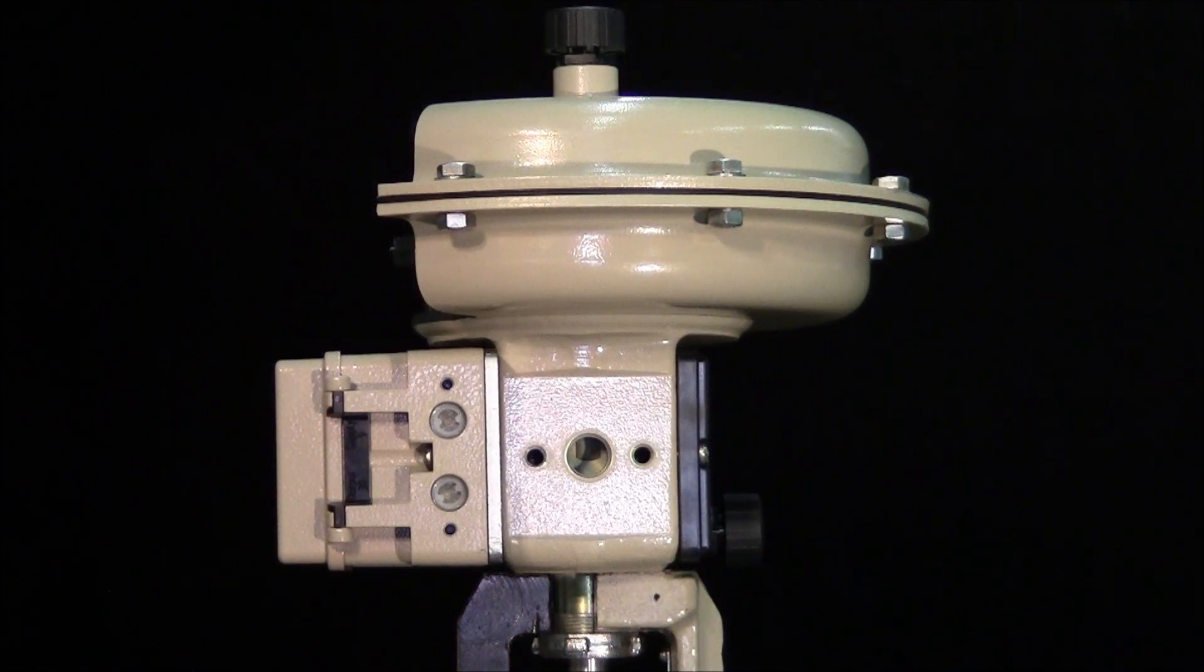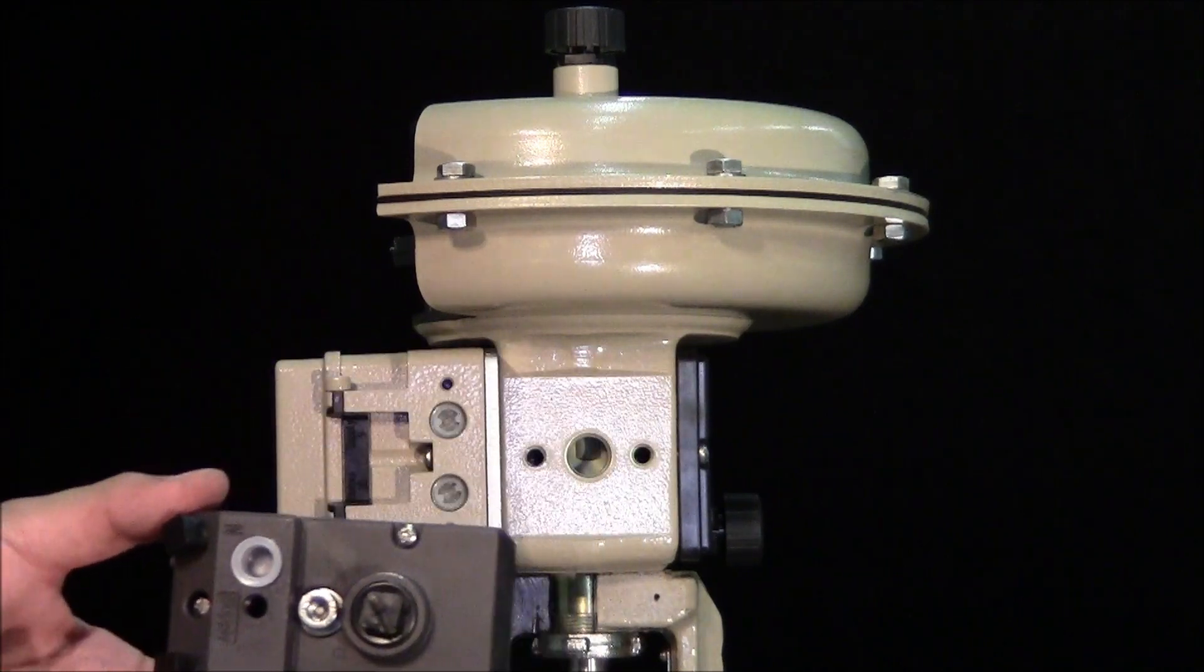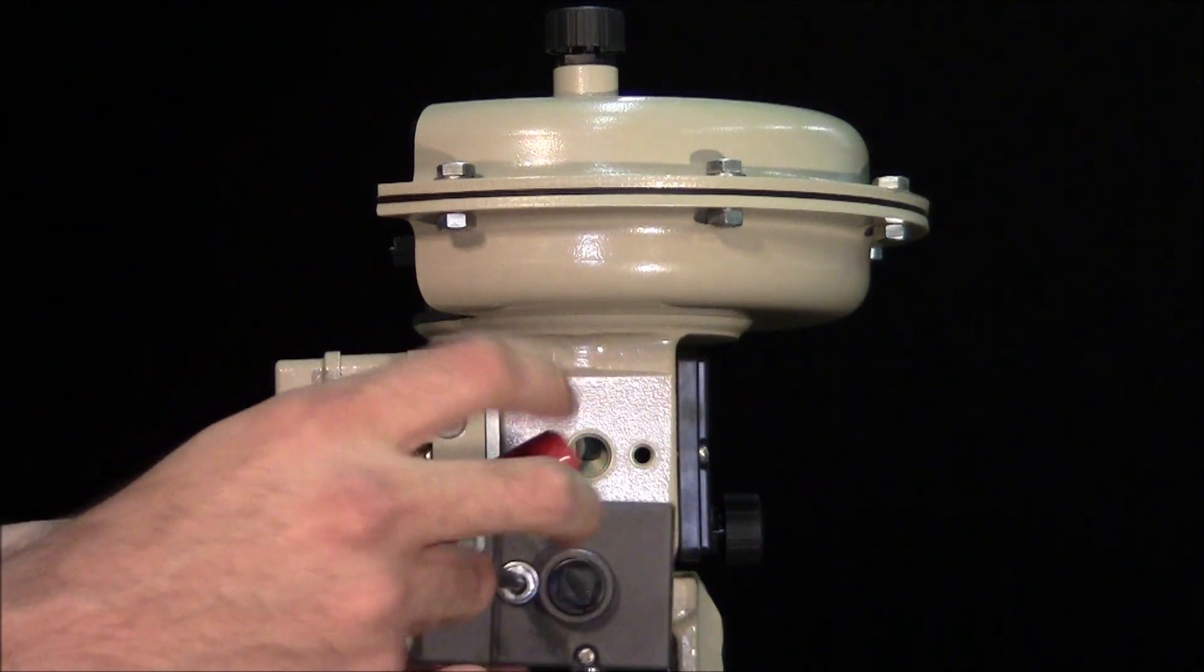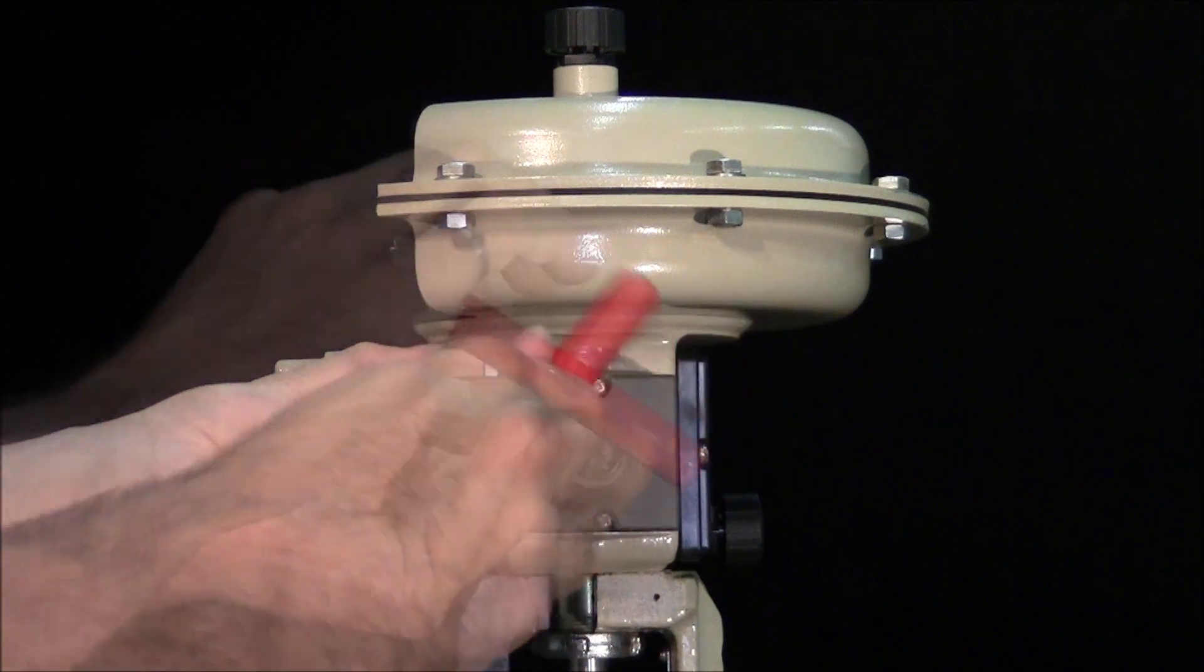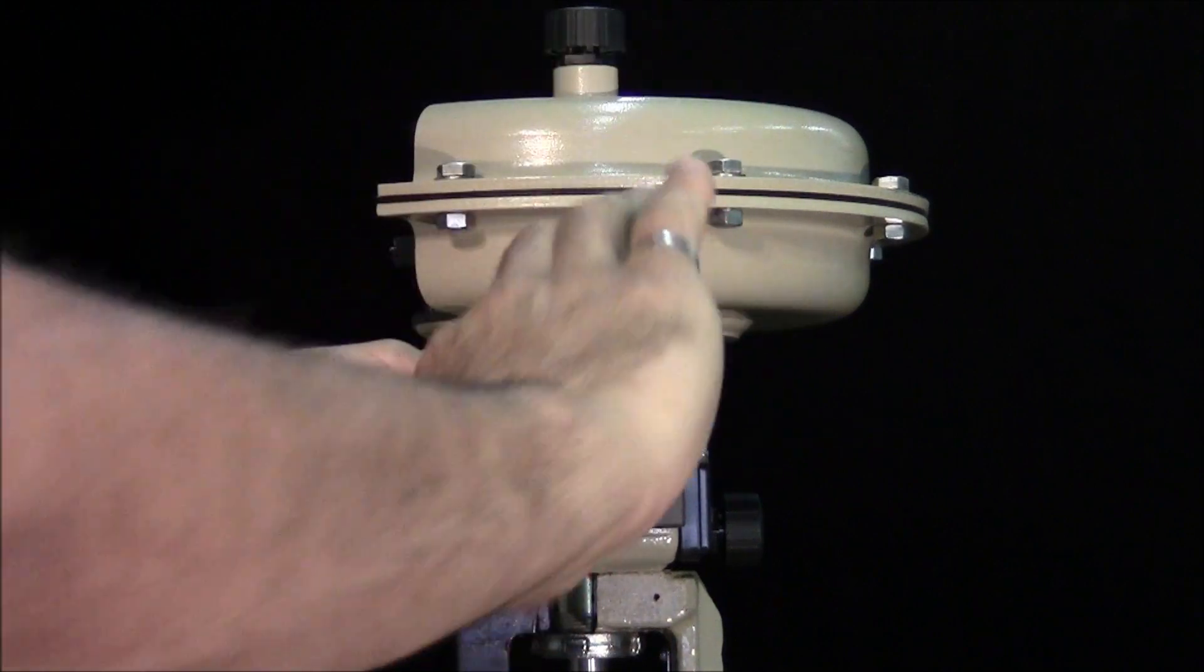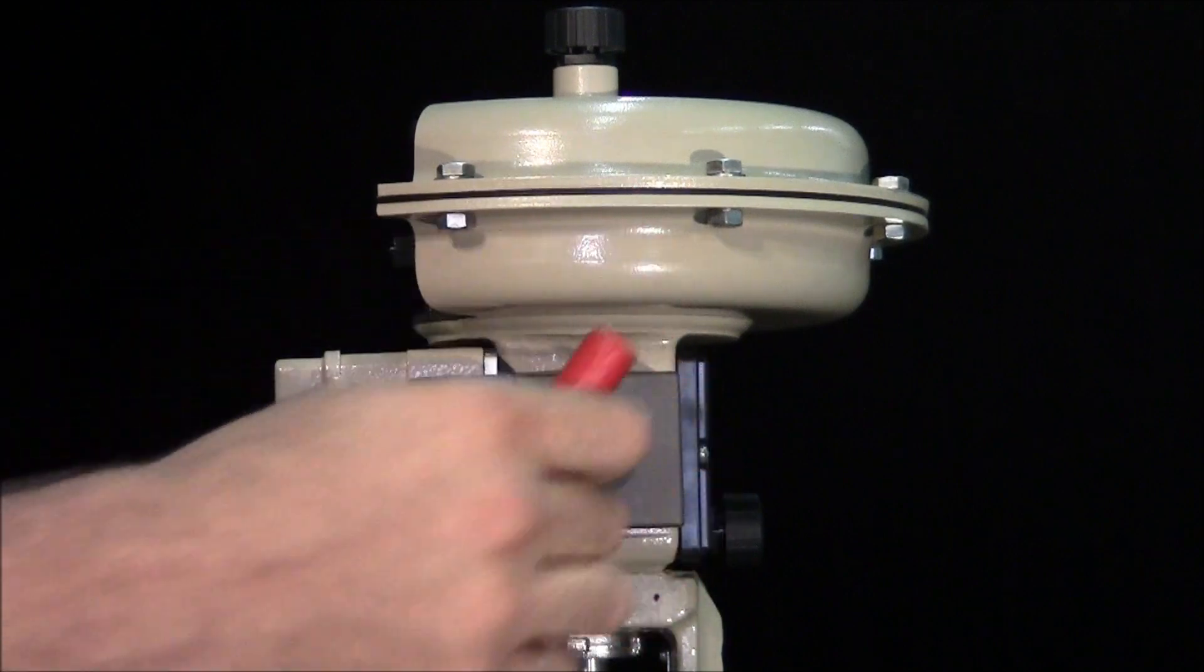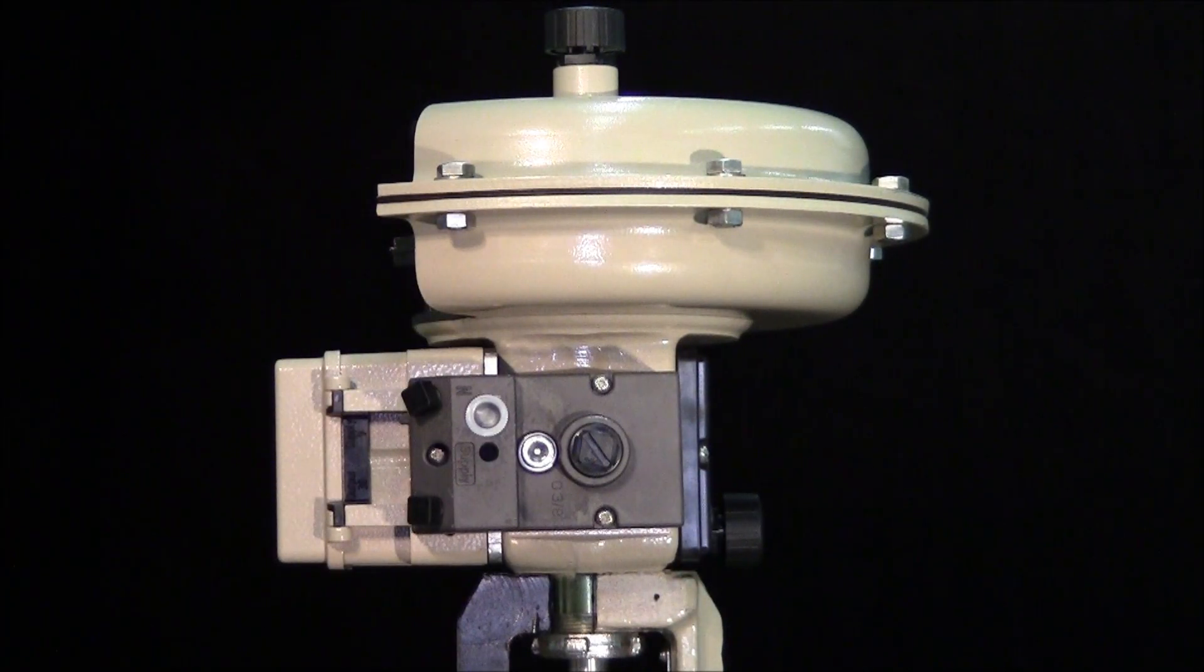As our actuator fails closed upon loss of air supply, we can use a connecting block to eliminate the need for tubing between the positioner and actuator. Securely mount the block, making sure all O-rings are in place.